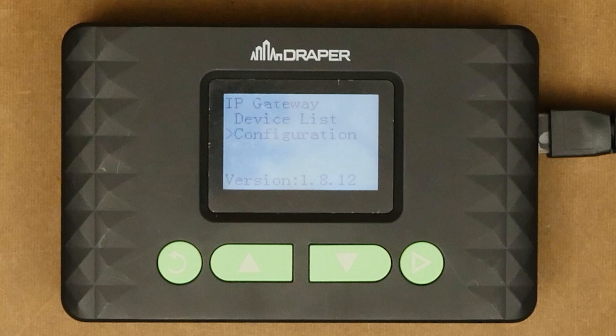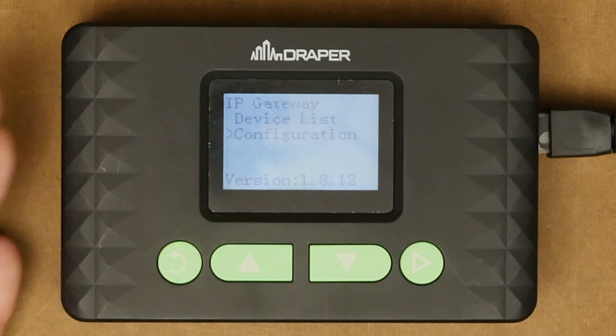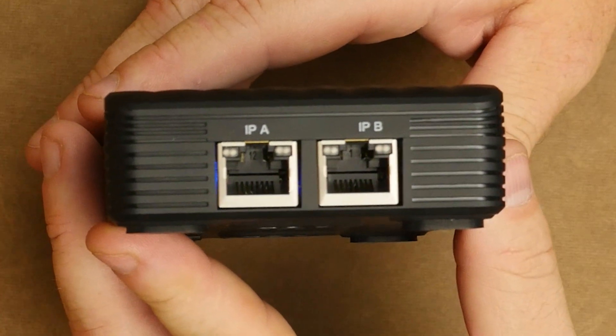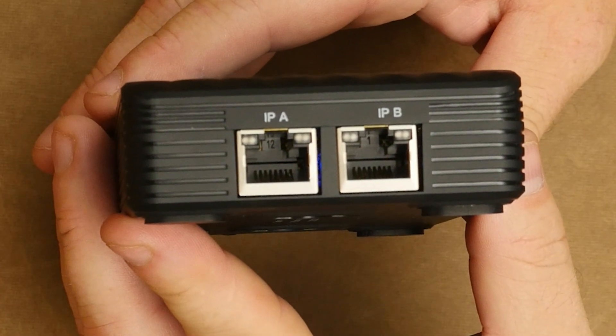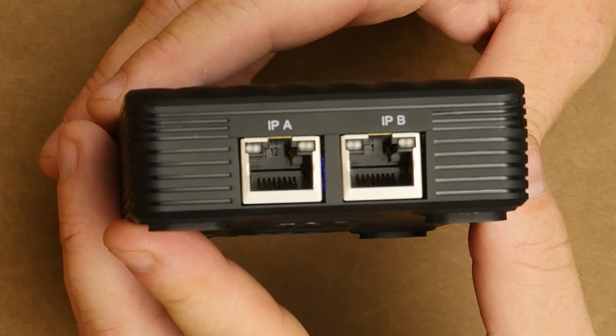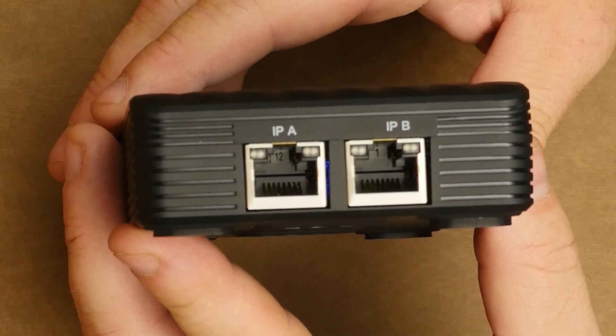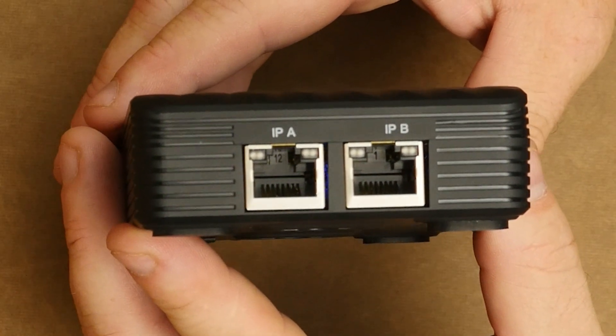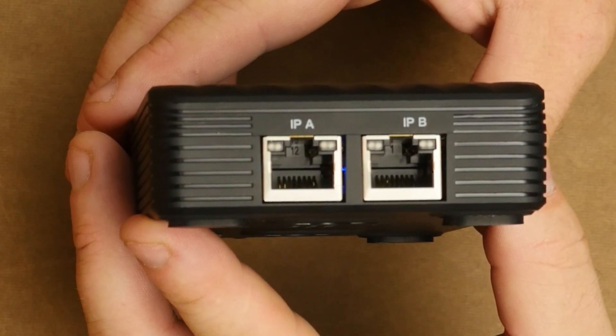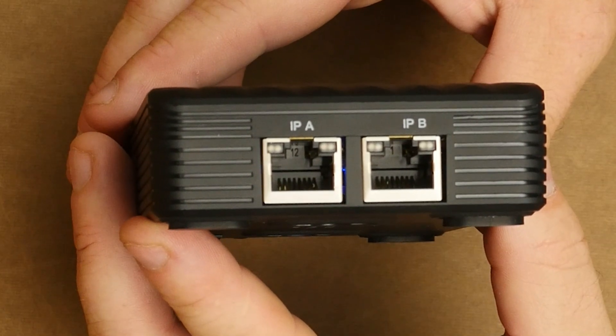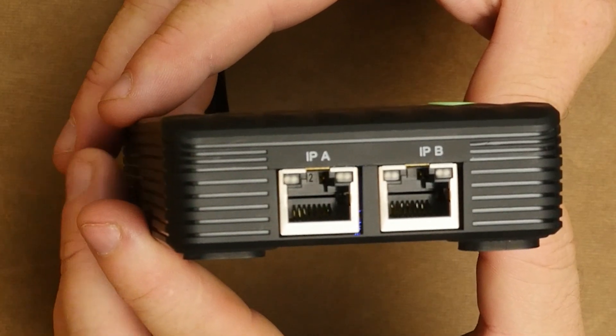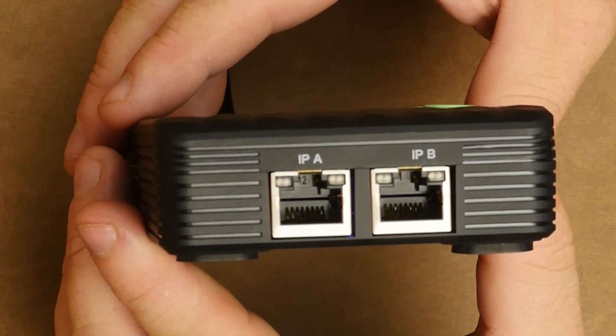Each IP gateway has two IP ports available, both on this side. If we turn this up you can see that we have an IPA and an IPB. These can be used to tie directly into a building network, or if we're building a dark network for the shade system you can use the IPA and IPB to wire IP gateways from floor to floor together to create one continuous communication network over IP.